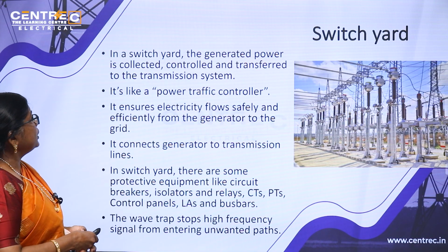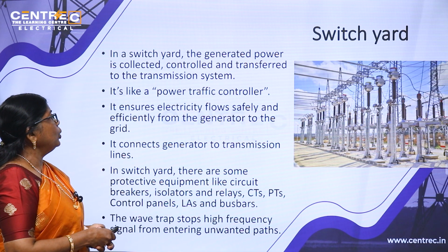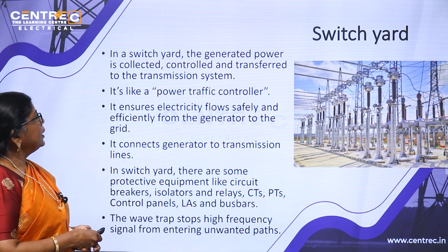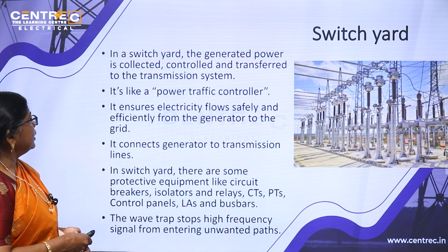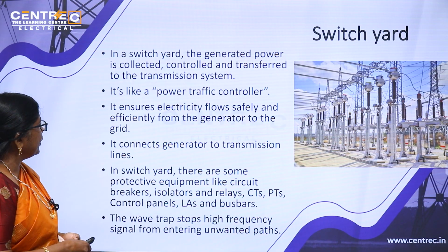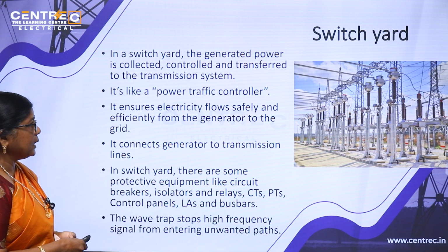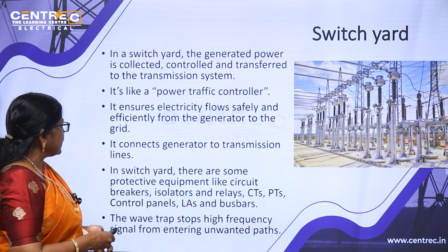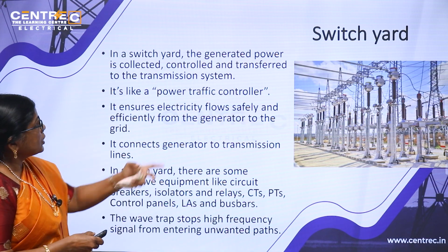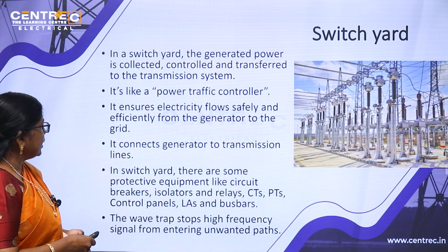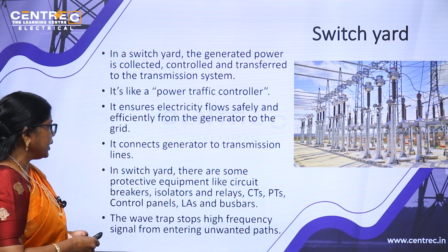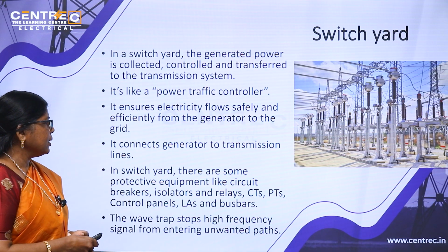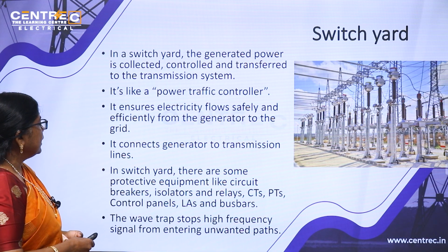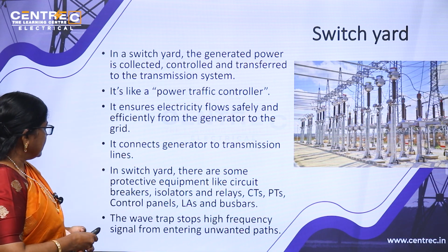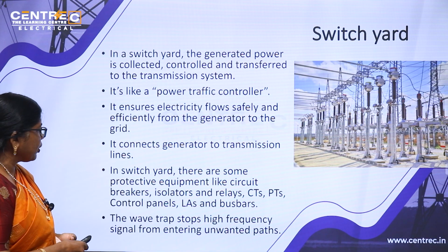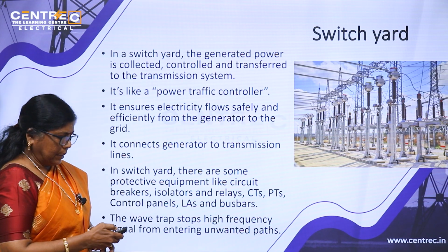Then the switchyard, because in a switchyard the generated power is collected, controlled, and transferred to the transmission system. It is like a power traffic controller. It ensures electricity flows safely and efficiently from the generator to the grid. It connects the generator to transmission lines. The figure shows an example of a switchyard. In a switchyard, there are protective equipments like circuit breakers, isolators and relays, CTs and PTs, control panels, lightning arresters and bus bars. The wave trap stops high frequency signals from entering unwanted paths.